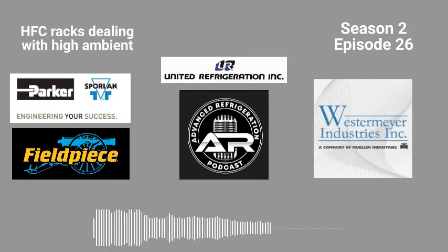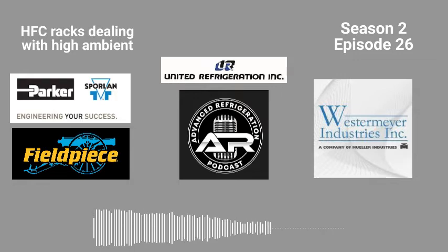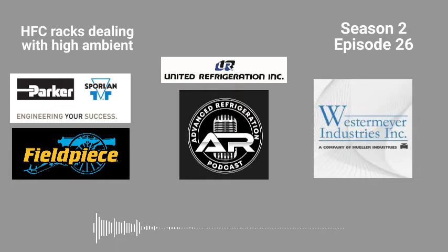Do not use coil cleaner on particular condensers or gas coolers that you see a tag on there that says Bronzeglow. Bronzeglow is an epoxy cover that they typically use near the oceans, so they get more longevity out of the condenser. That being said, if you use the condenser cleaner, the New Bright on there, it will shear all that stuff off and get it stuck in the condenser. And then your customer is going to be really pissed.